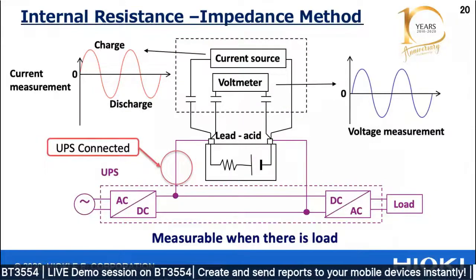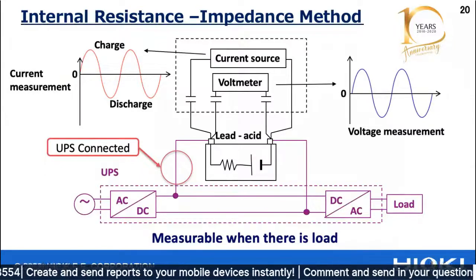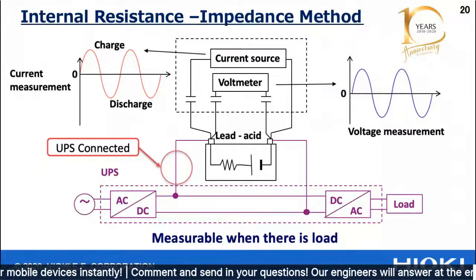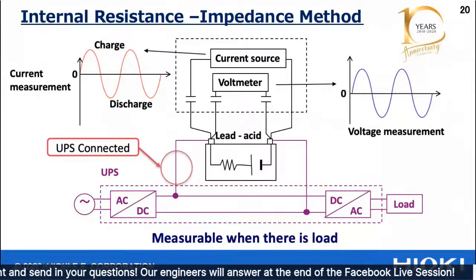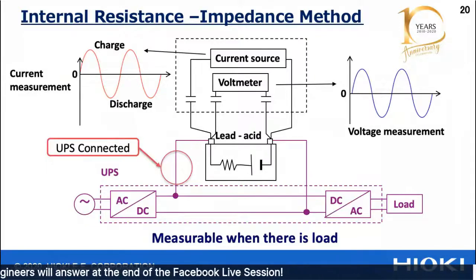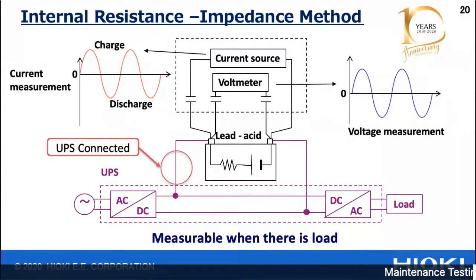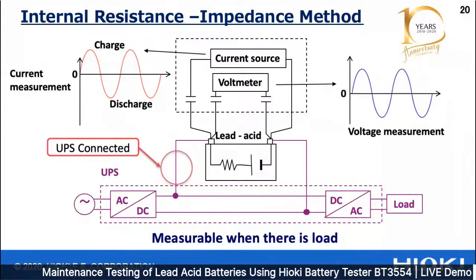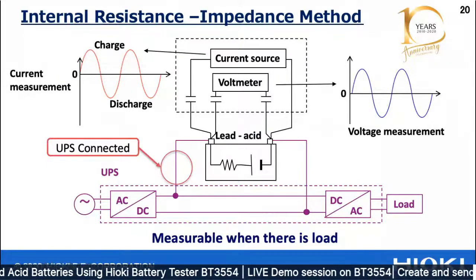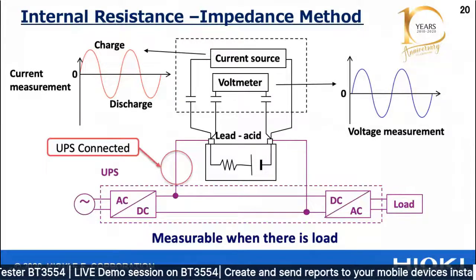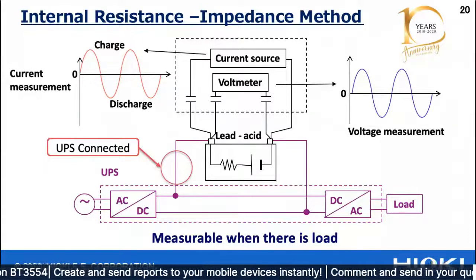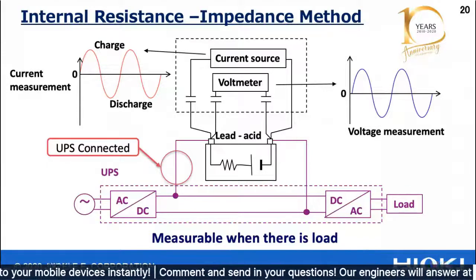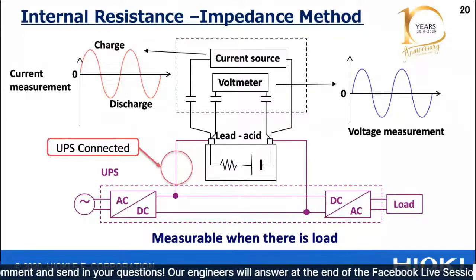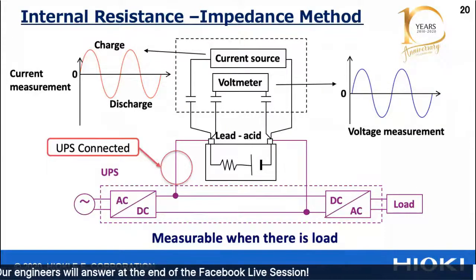Next we have the impedance method. HIOKI battery testers use the impedance method, still applying Ohm's law. This test is conducted during charge and discharge, and also when the batteries are connected to the load. We apply a 1 kilohertz AC signal, inject it into the battery, and the voltmeter measures the voltage across it, applying Ohm's law, R equals V divided by I, to give the internal resistance while the load is connected. It's important to note this method is applicable during charge and discharge, and also when the load is connected. So most battery testers are using the impedance method right now.